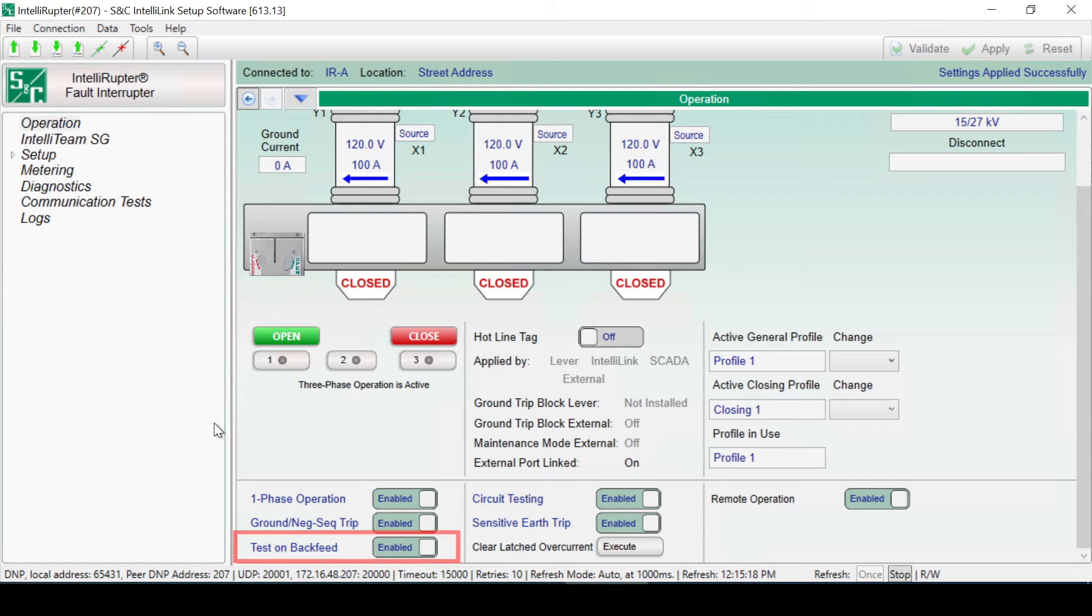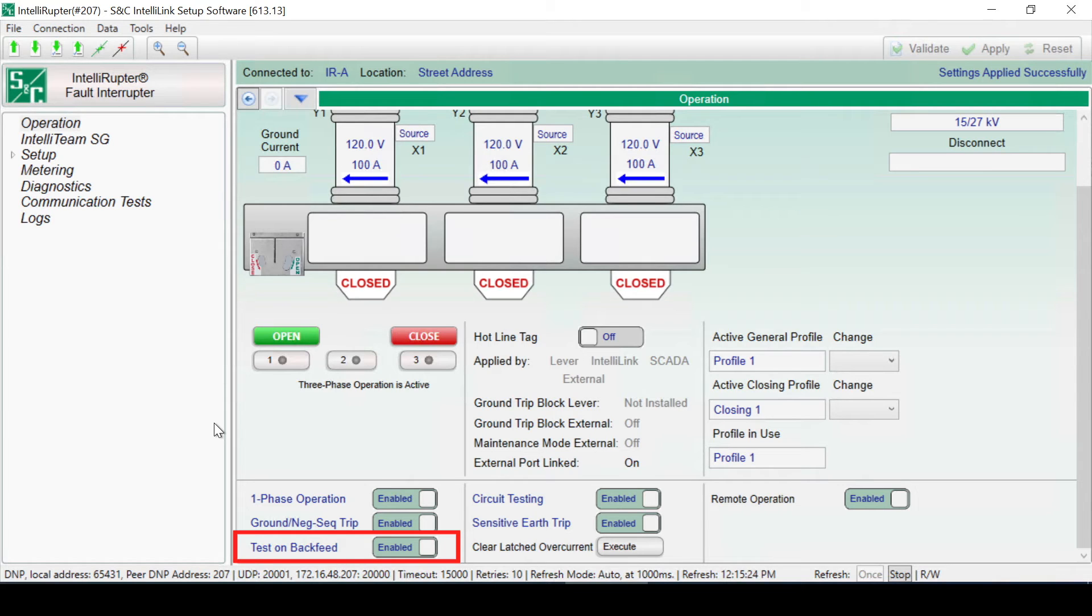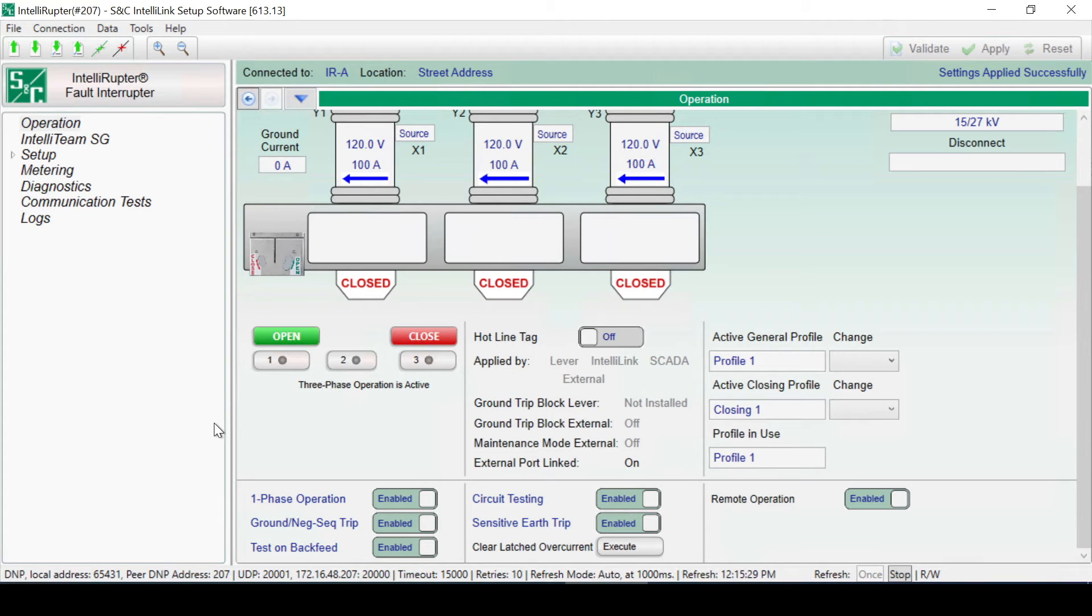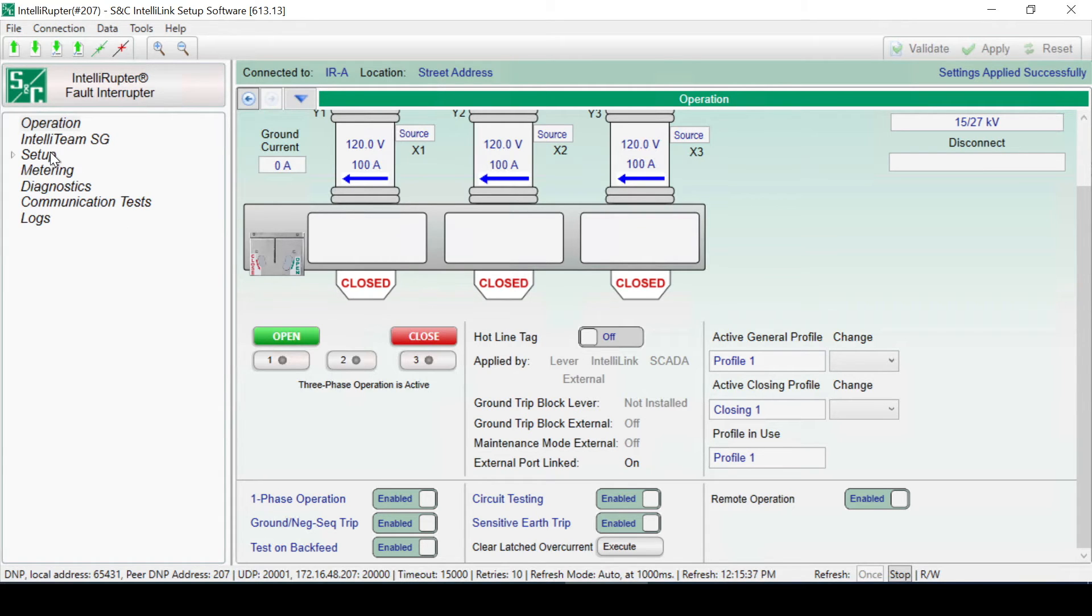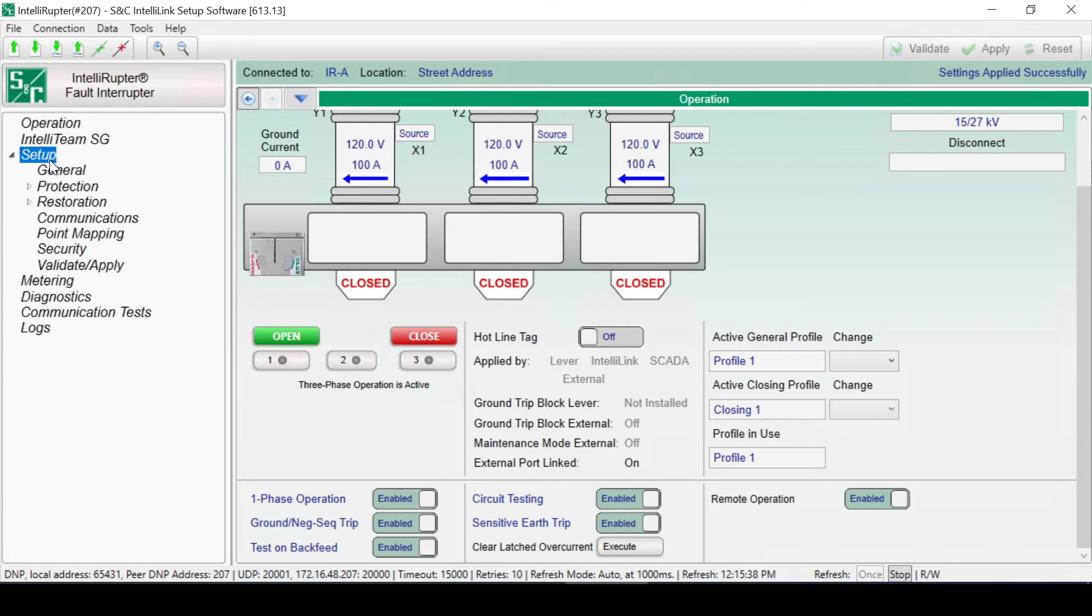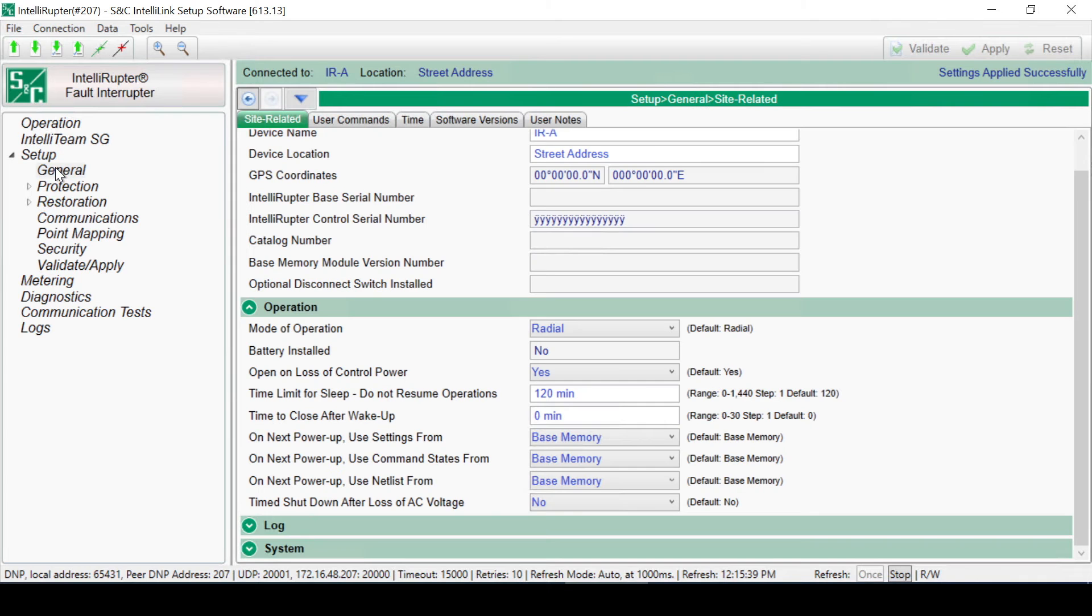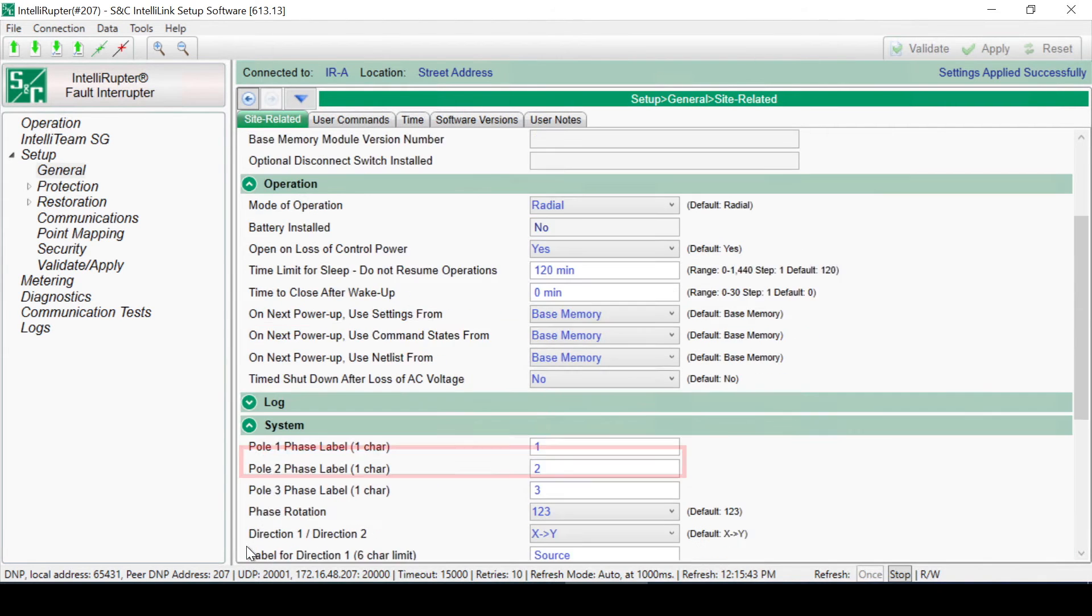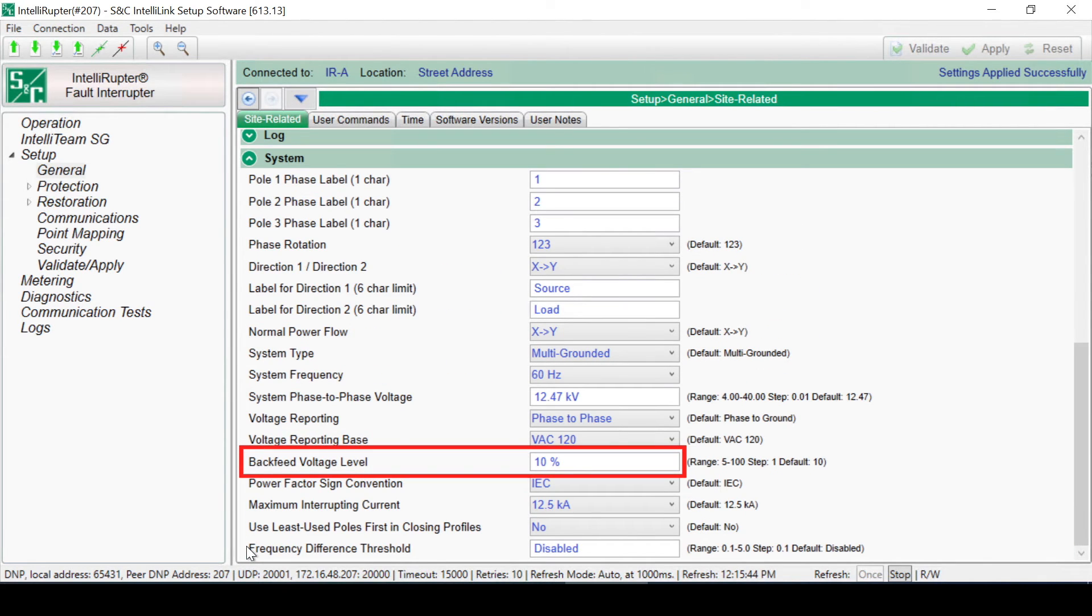When the Test on Backfeed slide control is enabled, it allows the switch to close with voltage on both sides of the IntelliRupter fault interrupter. This setting might be enabled in a case where a normally opened tie point is designed to allow closed transition. The backfeed voltage level can be set on the Setup, General, Site-Related, System page.